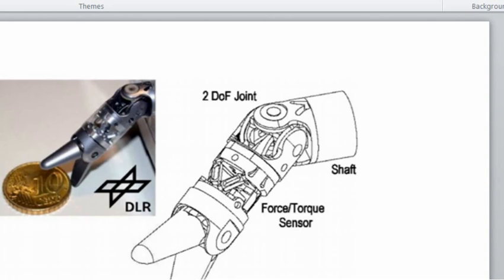It can measure force with a resolution of 0.25 newtons in axial directions and 0.05 newtons in the radial direction. The measurement range could be as high as positive or negative 20 newtons and 200 newton millimeters for the force and torque measurements respectively. So it's 20 newtons and 200 newton millimeters. The whole device has a diameter of 10 millimeters, which is acceptable for MIS. This is great.